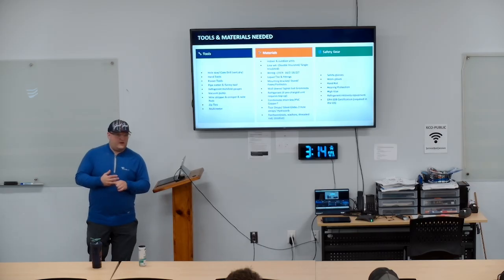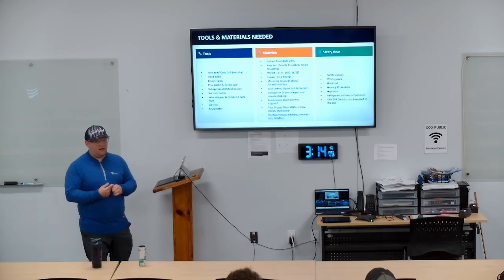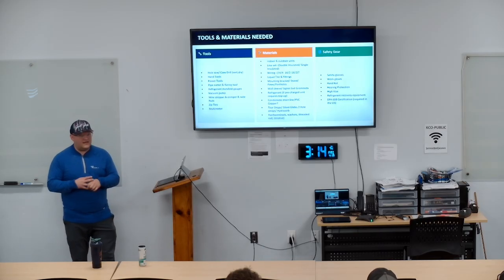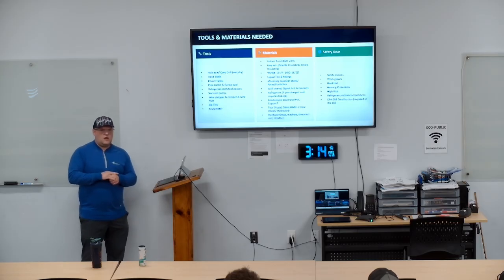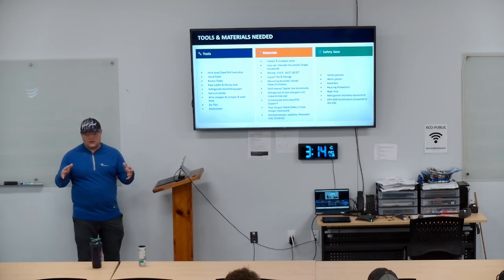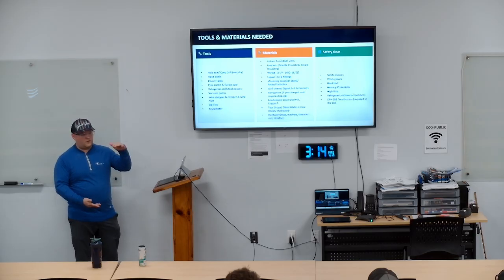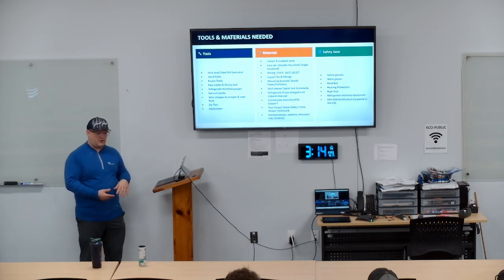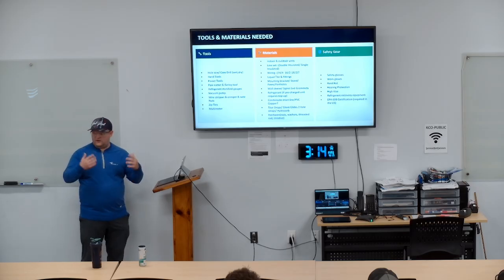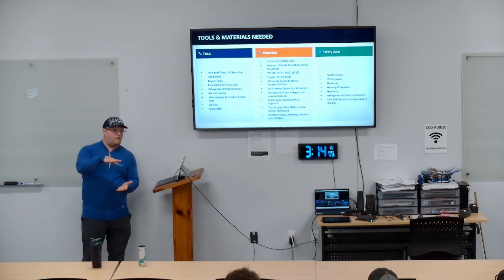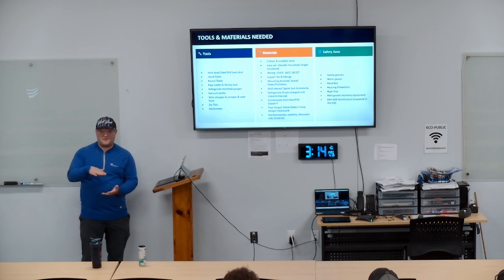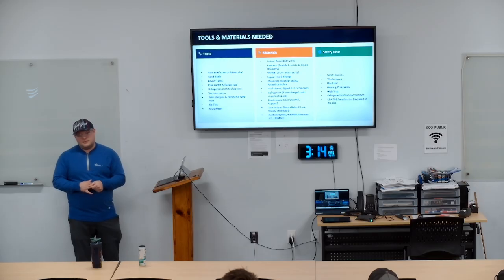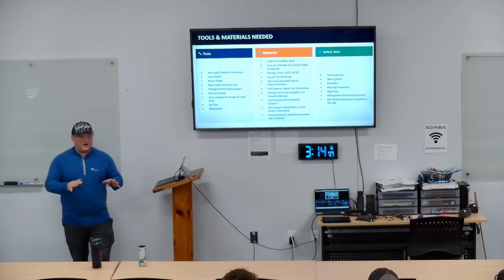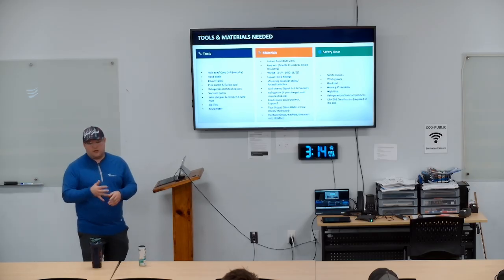So we've had to deal with it a couple times. And a lot of times you don't realize how bad it is. I can tell you, we have a job in Canton that we did, VRF systems underneath, 2 foot off the ground. Winter, it was really, really cold. Well, they defrost, full of water. There's 12 inches of ice under these units. So I'm like, we want them up. They all got to be up. If you don't see them, question it.